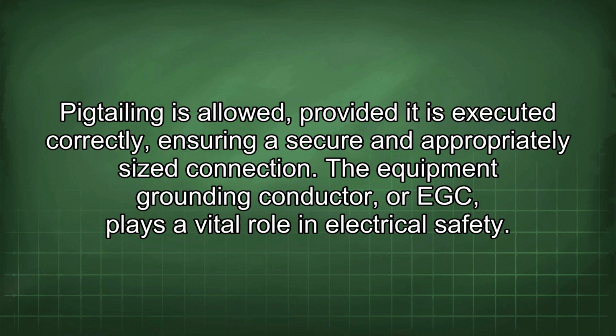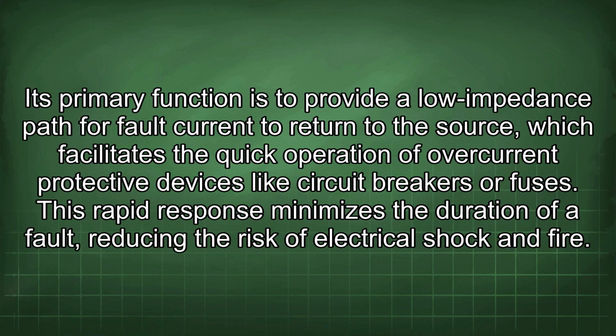The equipment grounding conductor, or EGC, plays a vital role in electrical safety. Its primary function is to provide a low impedance path for fault current to return to the source, which facilitates the quick operation of overcurrent protective devices like circuit breakers or fuses. This rapid response minimizes the duration of a fault, reducing the risk of electrical shock and fire.